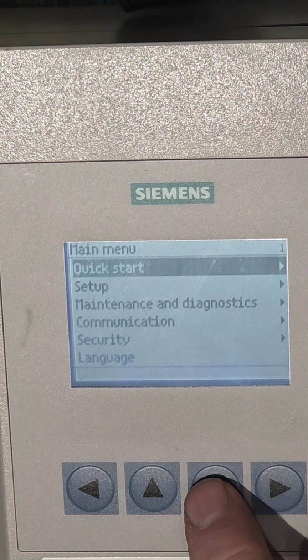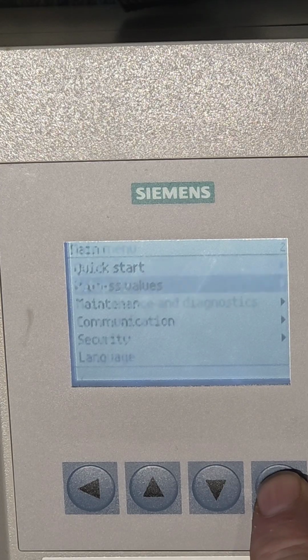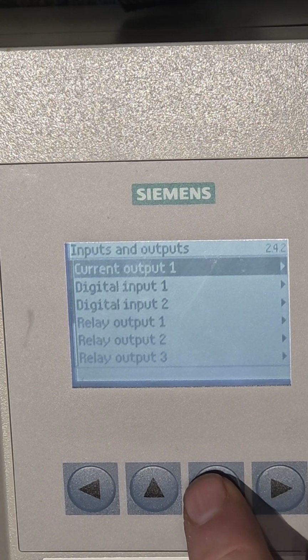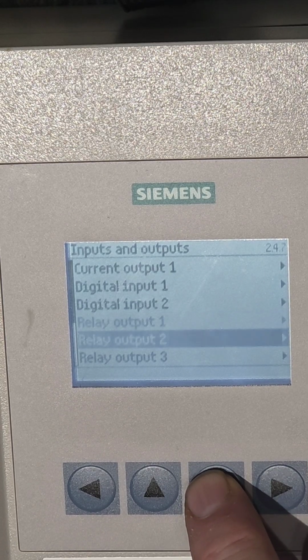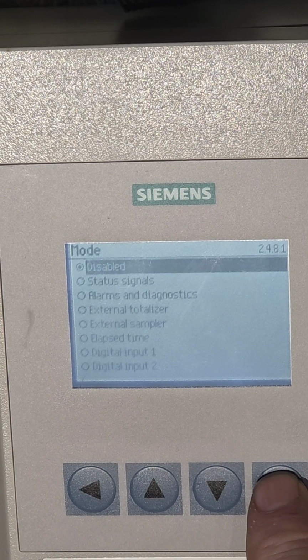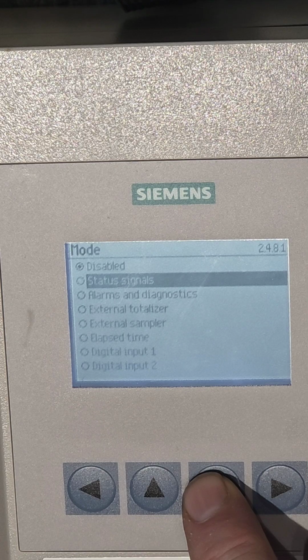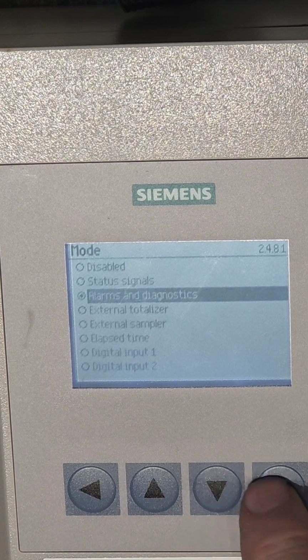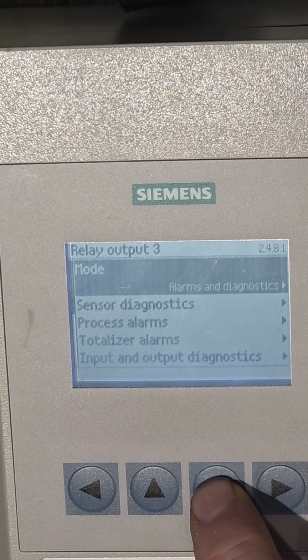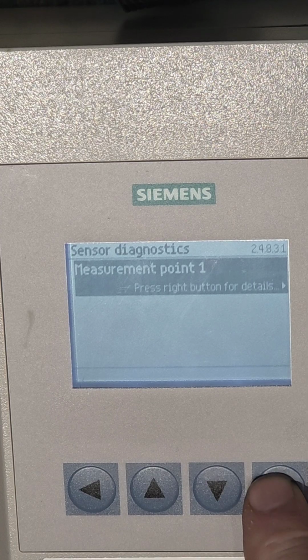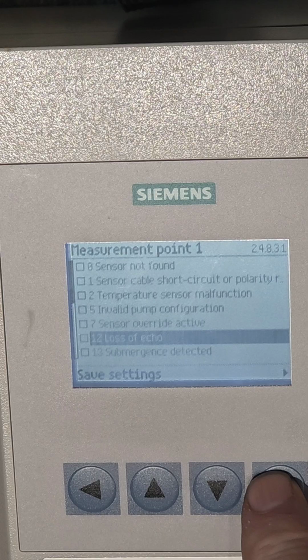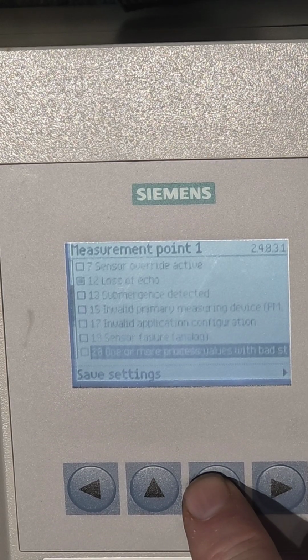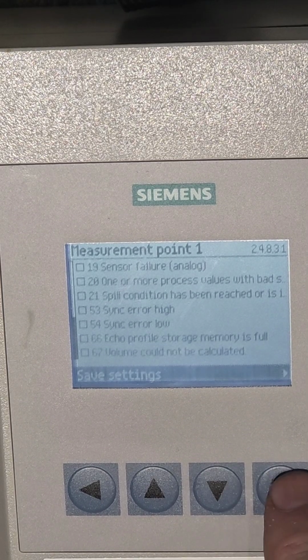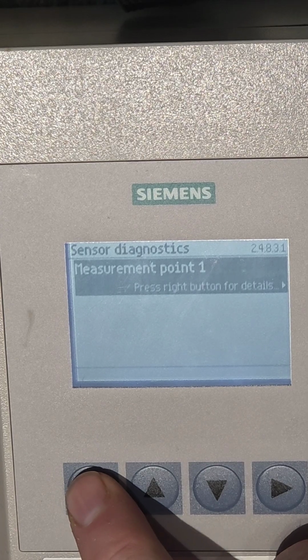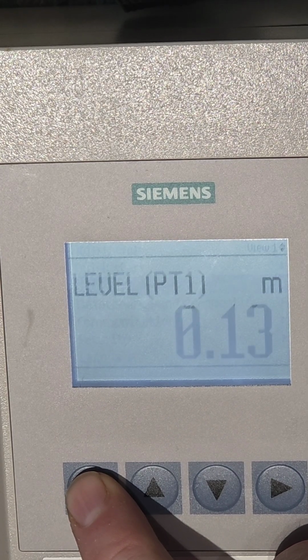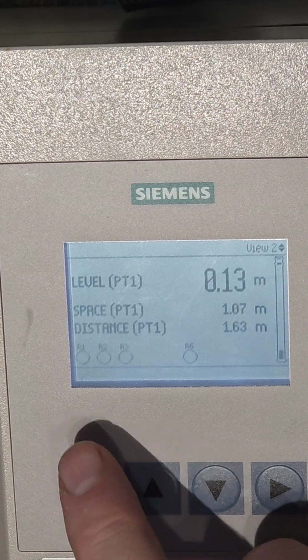Now I just want to set up my loss of echo, so down to setup, right click, inputs and outputs, go down to relay 3, I'm going to use for loss of echo, right click, mode, down to alarms and diagnostics, right click, click again, and down to sensor diagnostics, right click, and down to loss of echo, right click, and down to save settings, and right click, and left all the way back to run mode. Now if I press the down arrow, you'll see the 4 relays all programmed up.